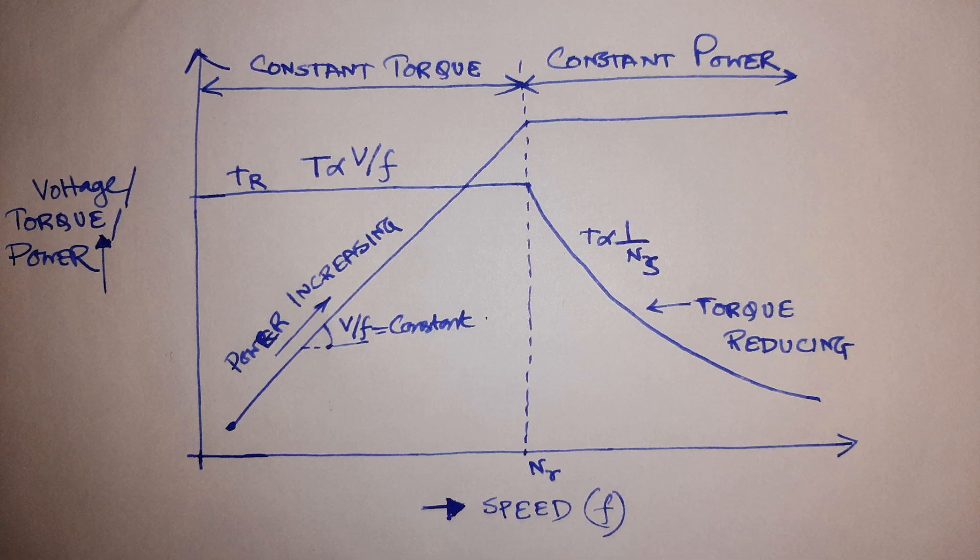In this graph we can see the relation between torque and power and how they are adjusted in VFD. On the x-axis, the speed is plotted, or the frequency, because speed is proportional to frequency. On the y-axis we have plotted voltage, torque, and power.